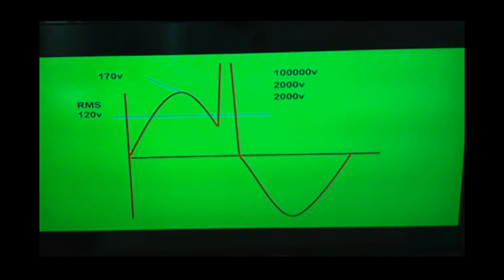But the problem here is meters will randomly explode for no apparent reason. And what causes the meter to explode is what are called transient voltages. In all reality, if we measure this electrical sine wave on an oscilloscope, for a 120 volt circuit, the top of that wave is going to be 170 volts. What we actually see with a meter is called a root mean square, or RMS, voltage, which is the 120. This is an average voltage.